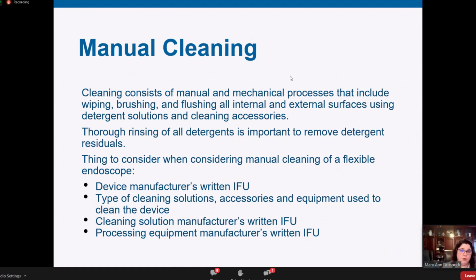But manual cleaning is a really thorough set of steps, sometimes over 100 steps just for manual cleaning. It involves wiping the outside surfaces, brushing all the channels that can be brushed, suctioning, flushing, all of that to remove that residual debris from the scope so we're more likely to achieve disinfection or sterilization. And even though there's not a lot of safety margin built into disinfection, that's why we need to make sure that these devices are being cleaned adequately every time.